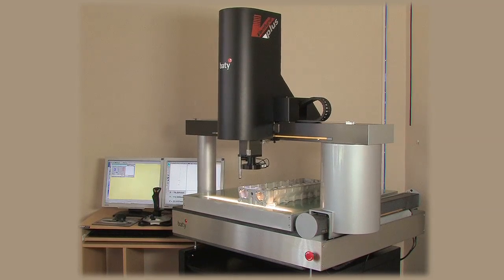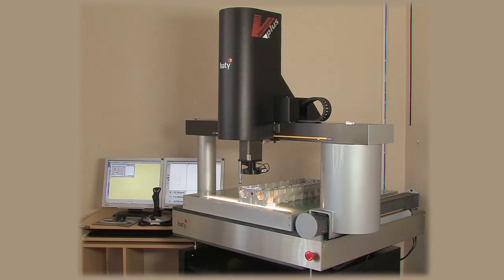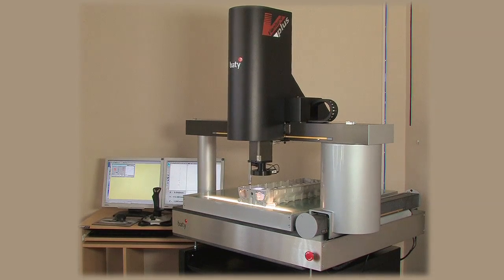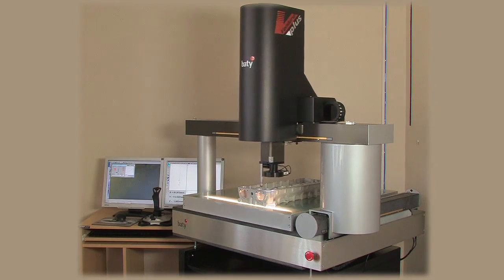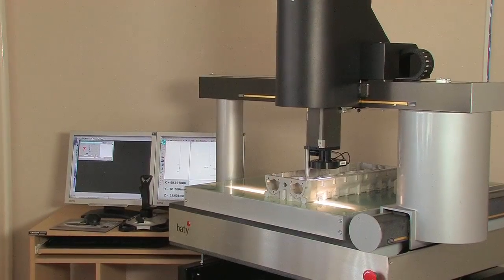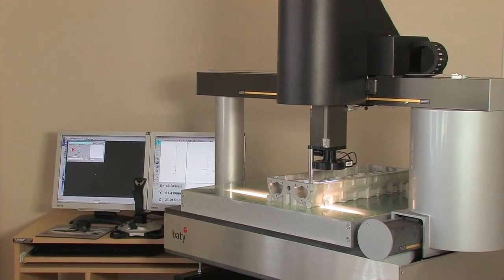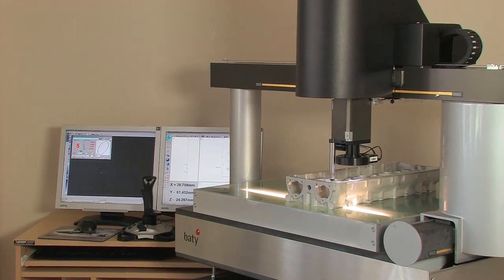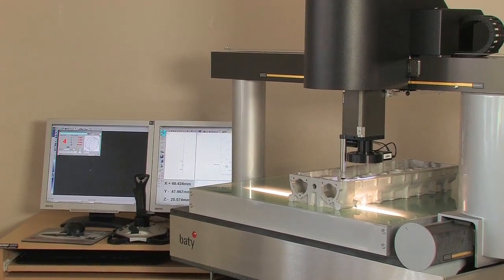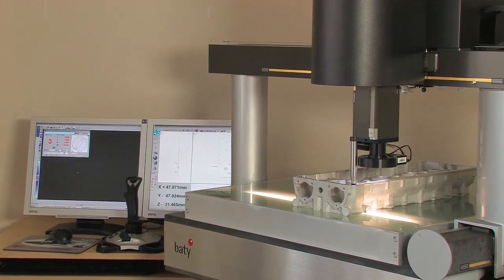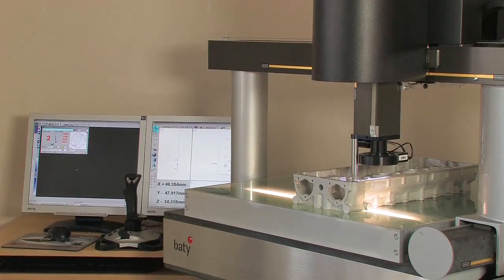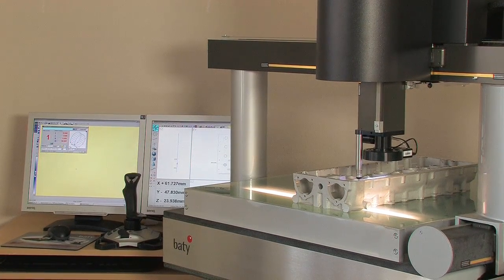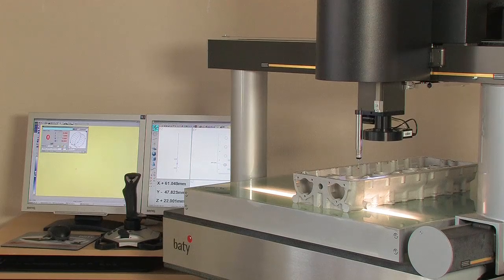The Venture Plus features a bridge construction which is all aluminum, resulting in low inertia and low thermal mass. Air bearings are used on all axes with a granite Y-beam for increased rigidity. The end result is a fast machine that will expand and contract more uniformly with temperature changes, ensuring minimal distortion and minimizing errors.